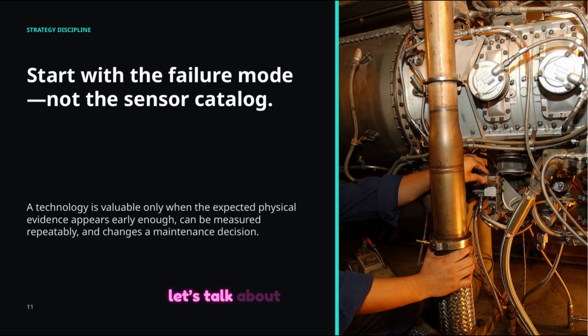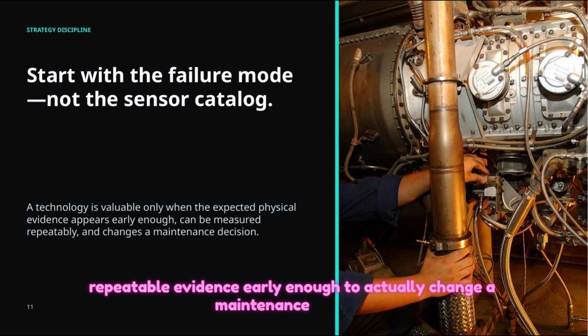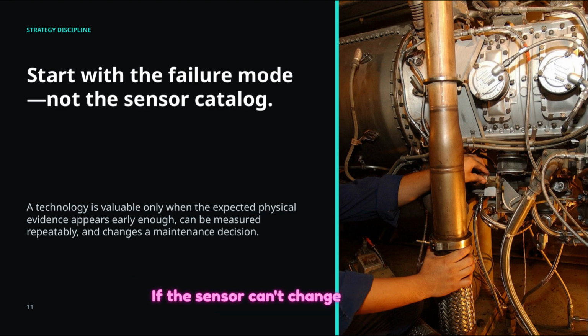Now, let's talk about strategy discipline. A common mistake is starting with a sensor catalog. You should always start with the failure mode. A technology only adds value if it produces repeatable evidence early enough to actually change a maintenance decision. If the sensor can't change what you do, you don't need the sensor.